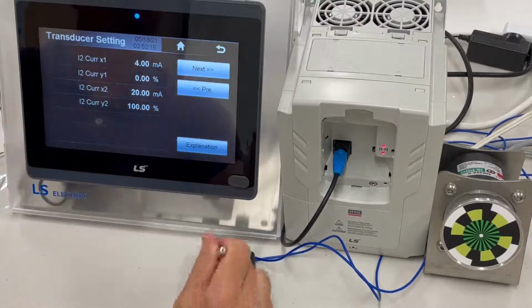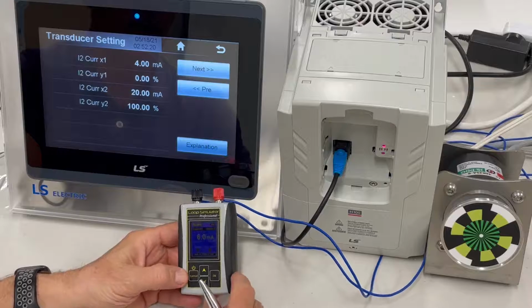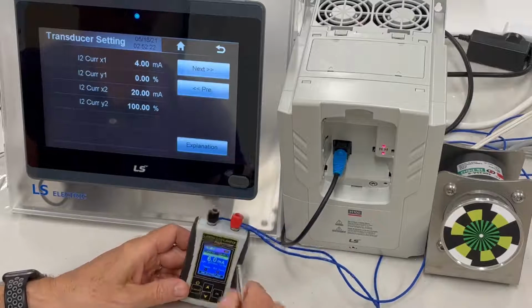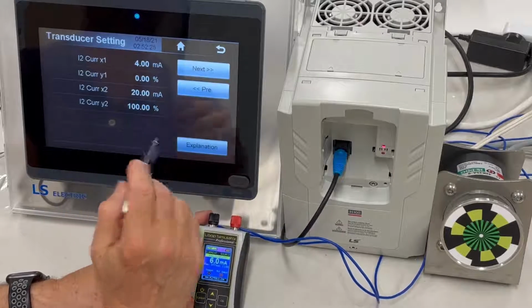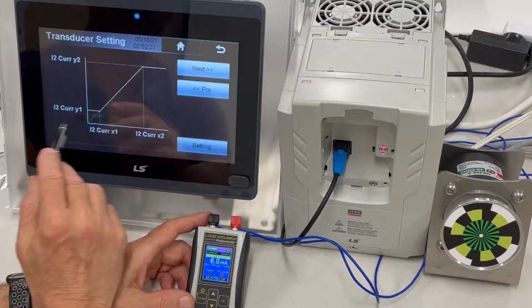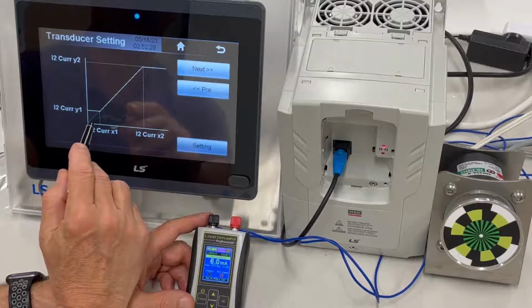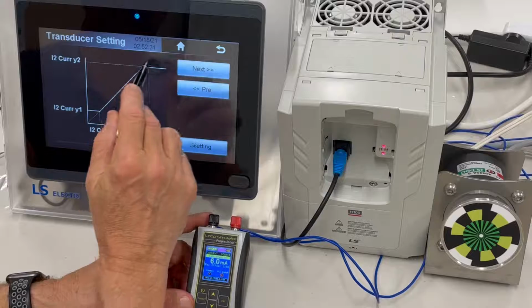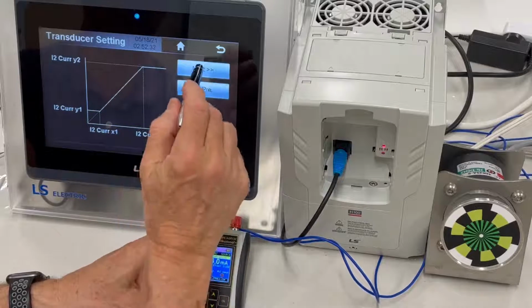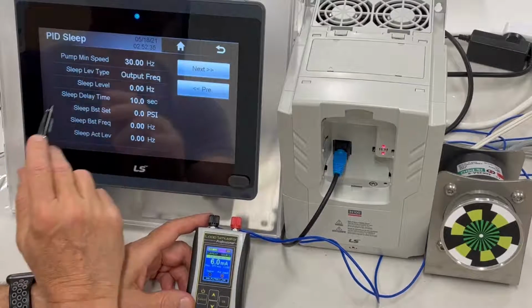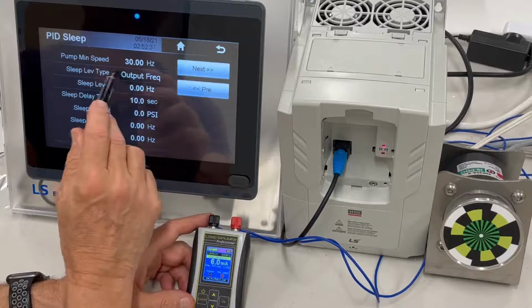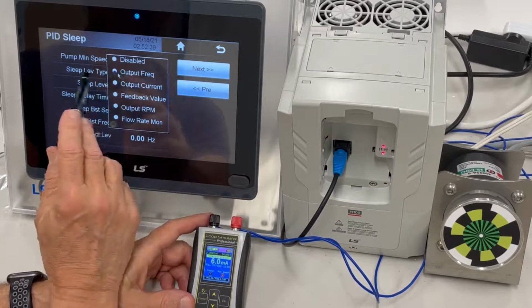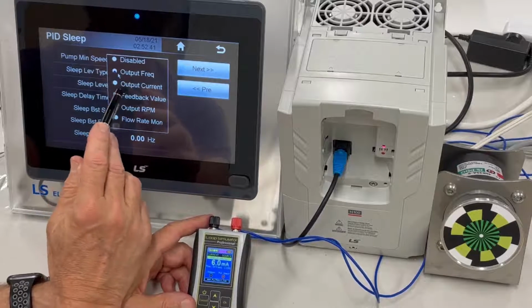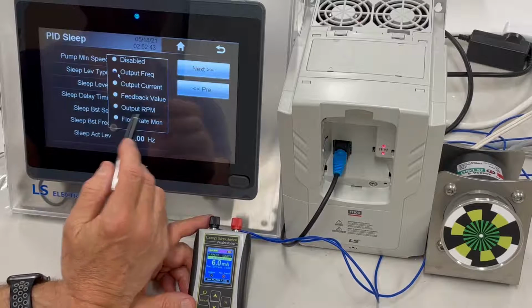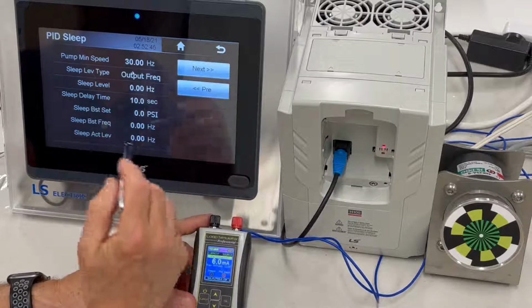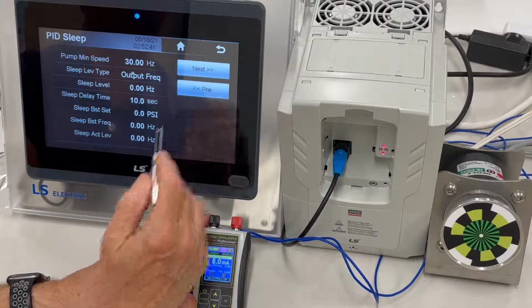Our transducer setting, which I said, remember, this is our little transducer here. It is basically a 4 to 20 milliamp setup, and if you needed to take a look at that graphically, we'll show you. There's the 4 is at 0, and then 100% of the scale is 20 milliamps. And then here's the PID sleep. We got it set for 30 Hertz. We have different types. You can disable it, output frequency, output current, feedback value, output RPM, and flow rate. All those there, and then here's other settings that you can use also.